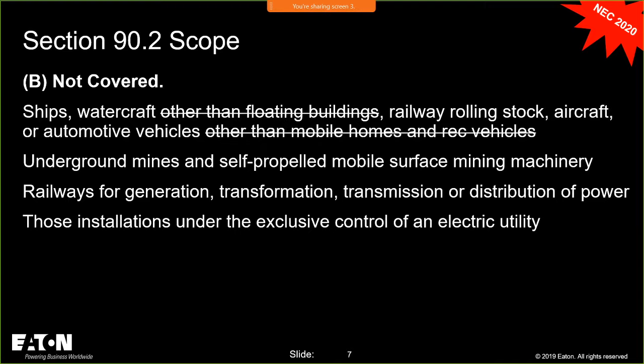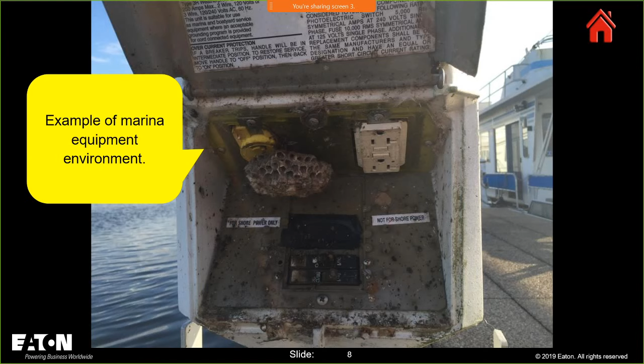So we got to recognize that, again, that's an example of what the environment of a marina provides to electrical distribution equipment. That's per pedestal. This was on a specific marina. I worked with an electrical inspector. We tested every one of the GFCI receptacles, and I think I recorded over 95% of them were supplying power but did not function correctly because of this environment that they are in. And that's just more reason why we need to really focus on marinas.